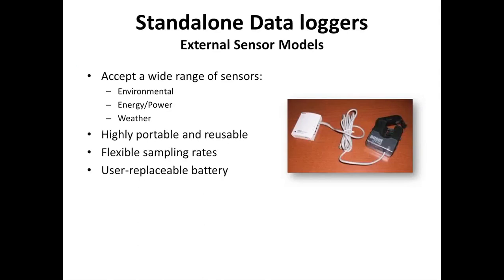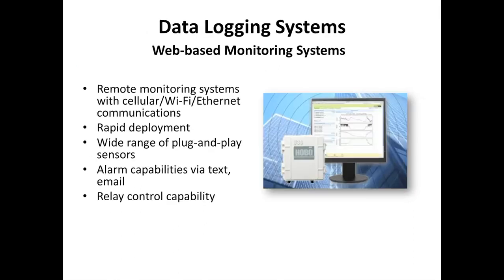We have external sensor models, sensors that have different inputs, maybe 4 channels worth of inputs that we can hook up. We can look at things like demand monitoring, power monitoring, power factor, and send it to a central data logger to log data at different intervals and read that information later.